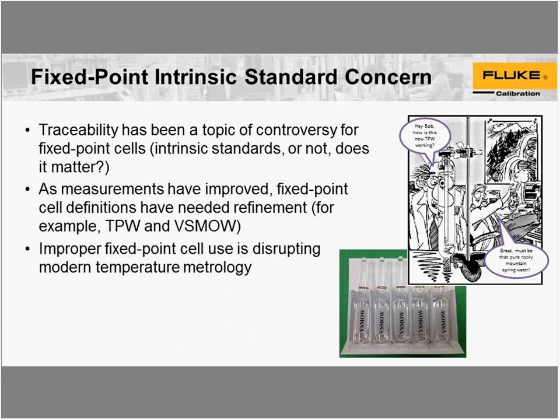So I thought it would be fun to pull this cartoon from our Hart Scientific website, where these two scientists or metrologists are looking at their new triple point of water. And when this cartoon was made, local water was put into the Hart Scientific triple point cells. But after the VSMOW initiative, we got everyone else transitioned over to VSMOW. So if you're using a cell from the VSMOW initiative, then there is a slight offset because of the isotopic content of the water.